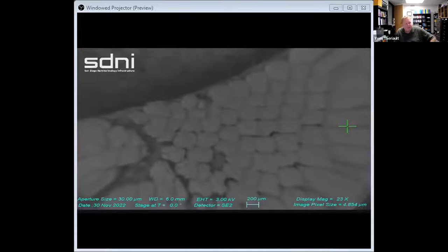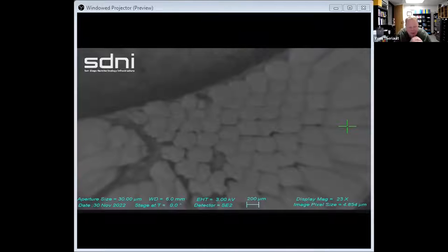For things where you can see nanostructures, I'm not entirely convinced that the remote control microscope is able to resolve that, because on our end over here, we have some stigmators that help focus when it's at pretty high magnification on the nanometer scale. So it might not be completely feasible for the remote access. Yeah, maybe the trigger is too coarse. Yeah, we would need to make the trigger finer or add stigmators or something. Yeah, we'll work on that actually. It's probably some programming, but we'll try to do that.